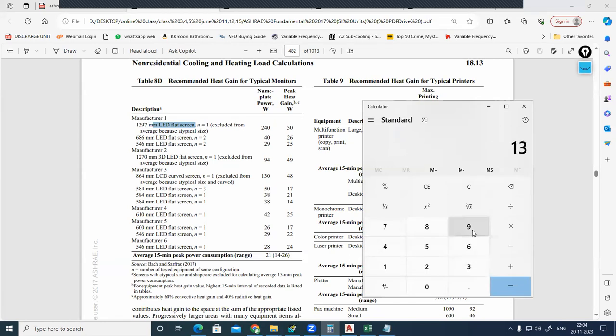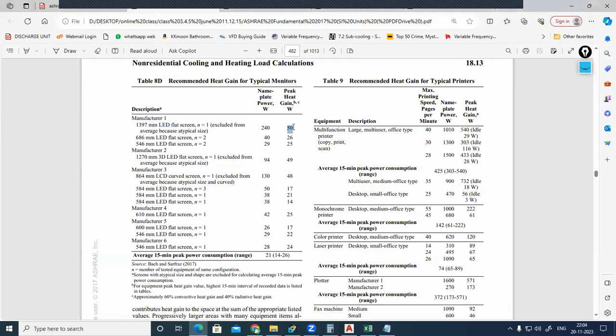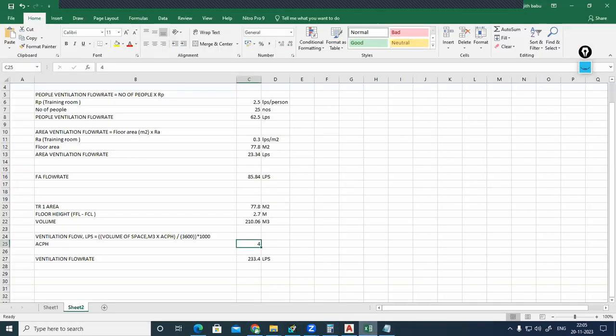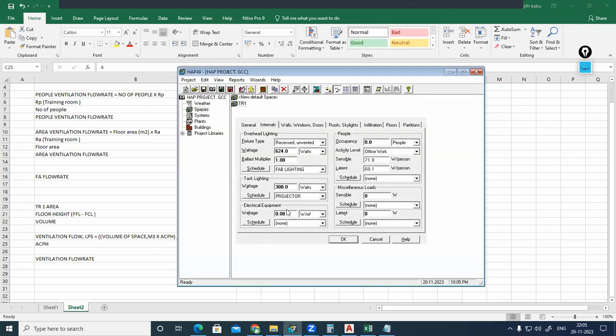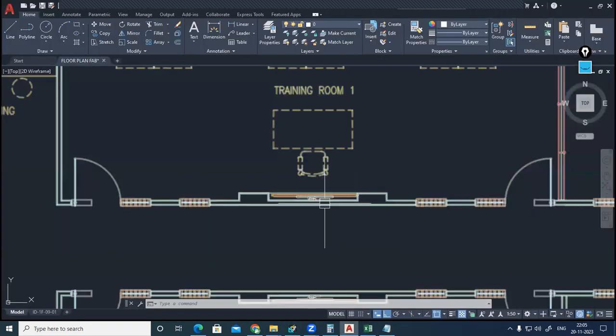1397 mm, how much is it? 1397 divided by 25.4 is nearly a 55-inch TV, or 50 inch or above. Nameplate power consumption might be 240, but you should consider a heat gain of how much? 50. So with respect to the average screen size, you can find from here how much heat has to be considered for the screen. 50, correct. So you can add that along with the electrical equipment, a 50 watts TV you can consider. But for any other detail, only a TV we are having here.